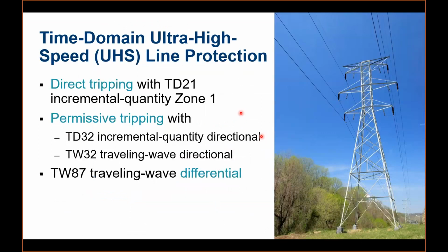All right. And then you can have standalone or direct tripping with this incremental quantity distance element. It is not dependent on any kind of communication with the remote end. So you can just independently apply this one and it will provide you direct tripping. Permissive tripping you can get with some POTT or comparison schemes with the help of these 2 elements, which are much faster in performance and they can act in a few milliseconds. And last but not the least is the differential protection that's based on the traveling wave, but you need a direct fiber between both the relays to achieve this.